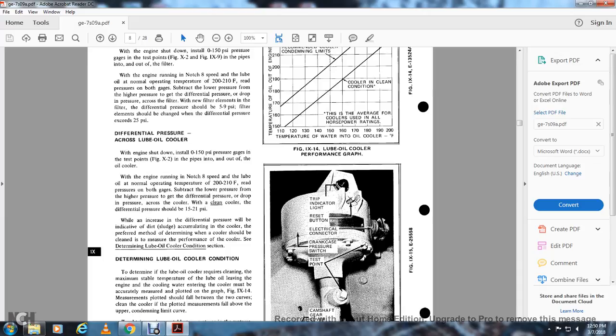Differential pressure across the lube oil cooler: With the engine shut down, install a 0-150 PSI pressure gauge at the test points in the inlet and outlet pipes of the oil cooler. With the engine running normally at notch 8 speed and lube oil at normal operating temperature (200°F), read the pressure on both gauges. Subtract the lower pressure from the higher pressure to get the differential pressure. For a new, clean cooler, the differential pressure should be 15 to 21 PSI. An increase in differential pressure indicates dirt or sludge accumulated in the cooler. The preferred method for determining whether the cooler should be cleaned is to measure its performance as described in the determining lube oil cooler condition section.